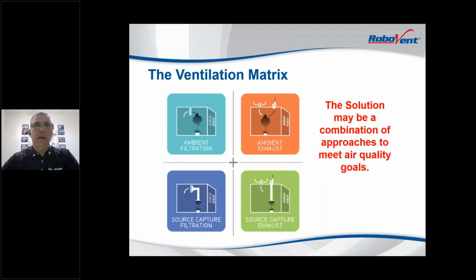So how do you protect your team members? A good way to look at it, from a 50,000 foot view, is what I call the ventilation matrix. It incorporates all the possibilities on how to ventilate the area and remove these types of airborne particulates from the process. In the upper left-hand corner is what we call ambient filtration. It's simply putting a system in the facility and pulling in air from anywhere, not from the machine or the metalworking fluid process, but just ambient air in that space, filtering it and returning it to that same manufacturing space. Below that, the bottom left, is source capture filtration. It's connecting something directly to the process, whether you have a metalworking machine, the CNC machine that's fully enclosed, and you duct that cavity, that process, to a filter to remove the contaminants and return that cleaned, filtered air to the manufacturing space. That's source capture filtration.